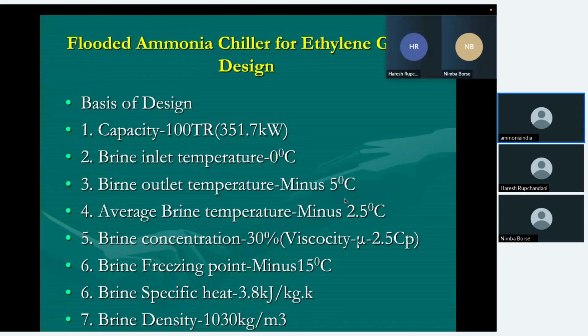The brine concentration is 30%. Viscosity, or mu, is 2.5 cP. The brine freezing point should always be at least 10 degrees lower than the brine outlet temperature. Here the brine outlet temperature is minus 5, so the brine freezing point should be at least 10 degrees below that. So such a concentration should be selected. Brine specific heat is 3.8 kilojoules per kg. Brine density is 1030 kg per meter cube.